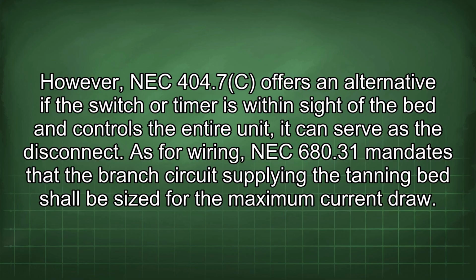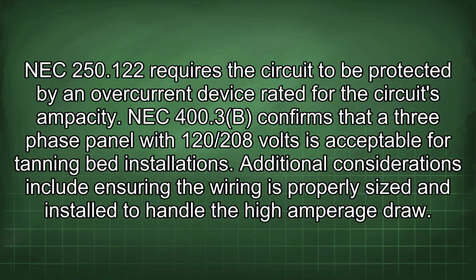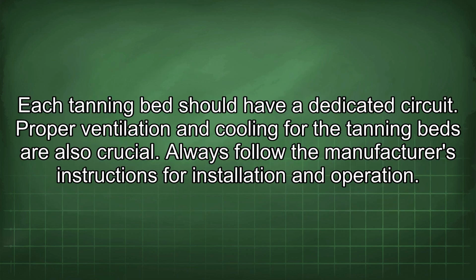the disconnect. As for wiring, NEC 680.31 mandates that the branch circuit supplying the tanning bed shall be sized for the maximum current draw. NEC 250.122 requires the circuit to be protected by an overcurrent device rated for the circuit's ampacity. NEC 400.3b confirms that a three-phase panel with 120/208 volts is acceptable for tanning bed installation. Additional considerations include ensuring the wiring is properly sized and installed to handle the high amperage draw. Each tanning bed should have a dedicated circuit.